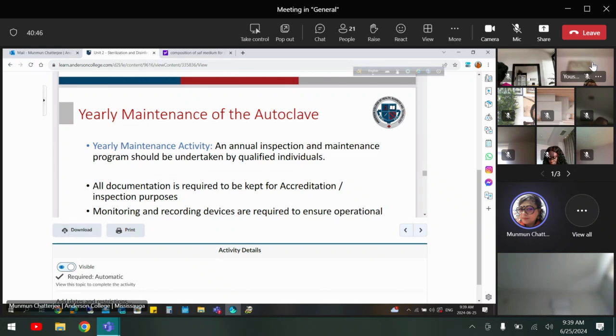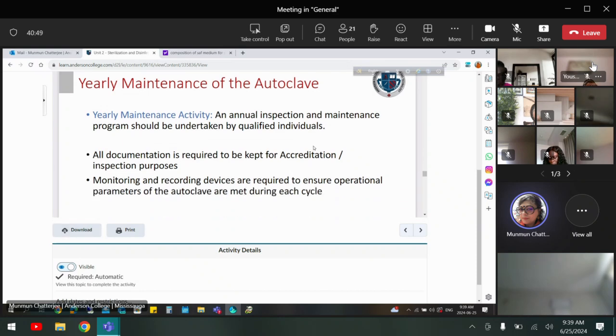Yearly maintenance: annual inspection, as for the majority of instruments, they have to come and check the instruments annually. That is the duty of the organization for quality assurance and quality management. All documentation is required to be kept for accreditation inspection purposes. So that's why you are always told accreditation, accreditation, accreditation, so that you are doing the daily maintenance. When you are using the autoclave, you are logging the temperature, pressure, who ran it, for how long, and if there is any damage or any comments. If there is anything, nobody takes care of it or it has not been reported. It is not only for the autoclave, it is mandatory for all instruments.